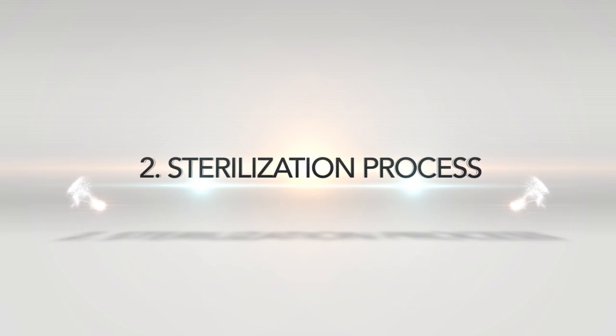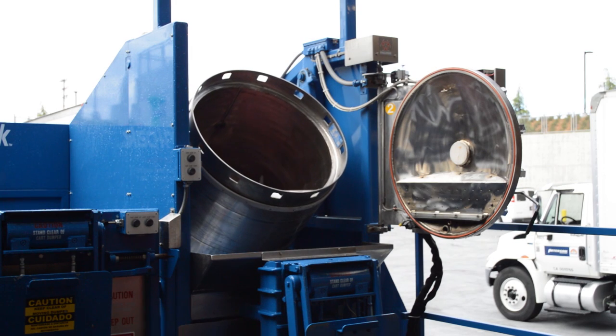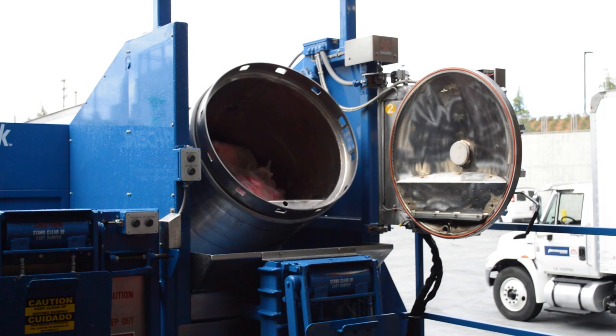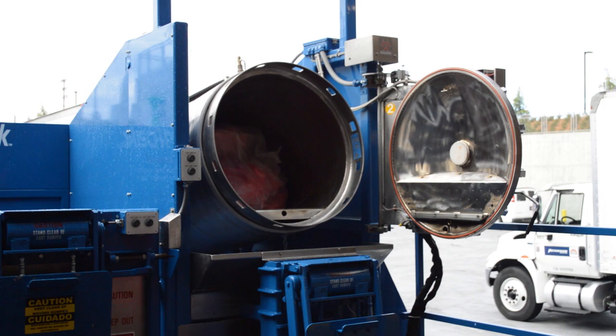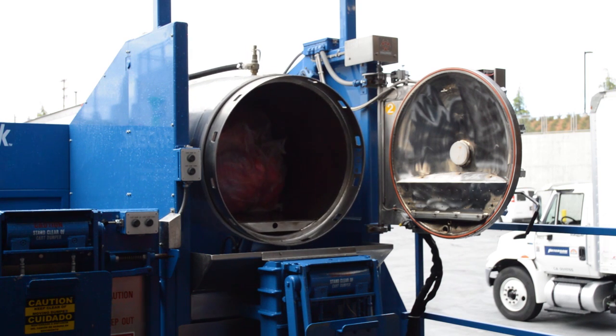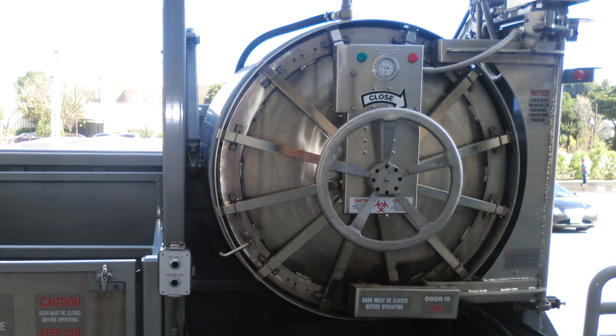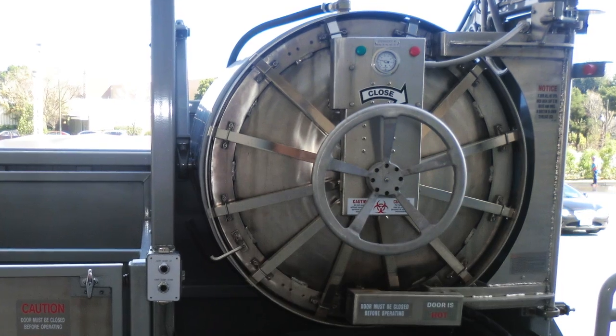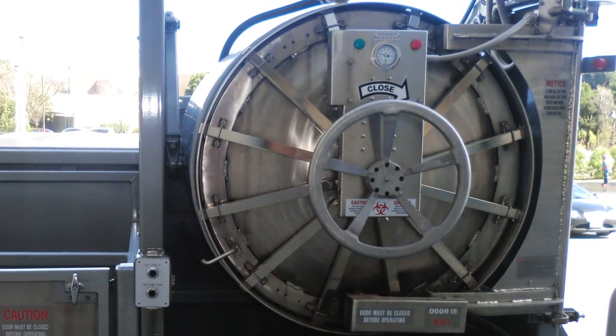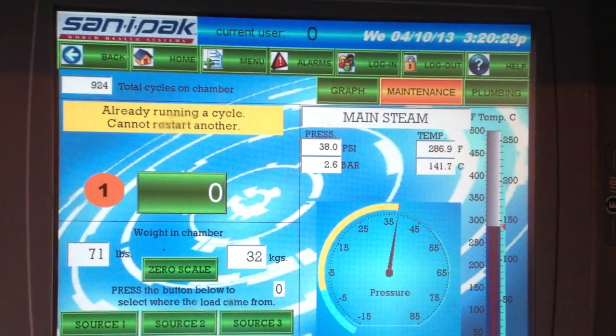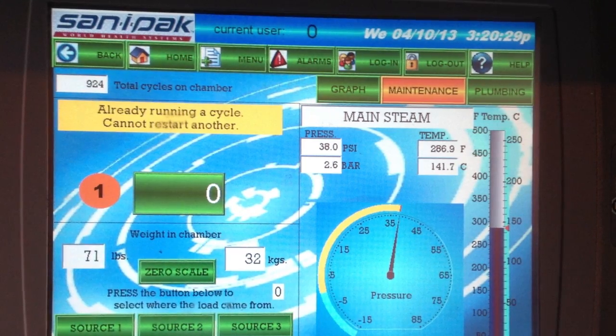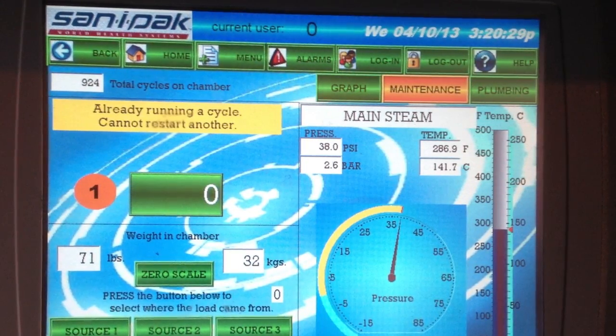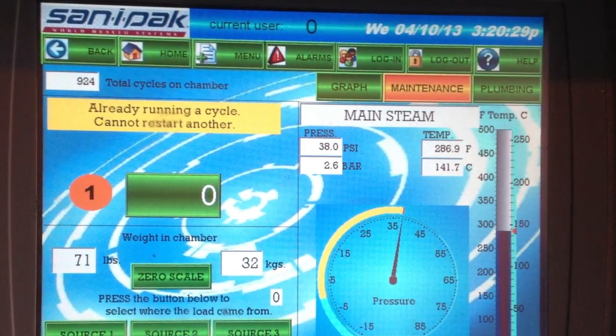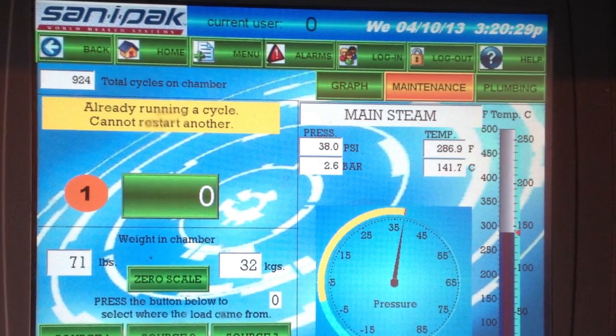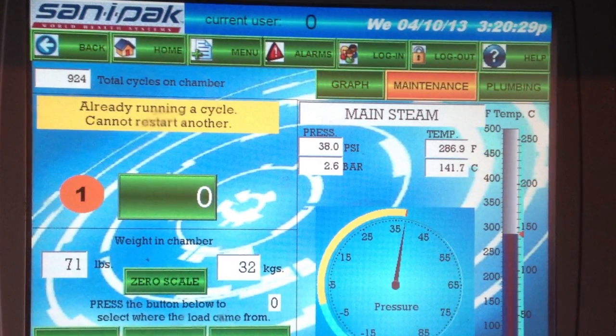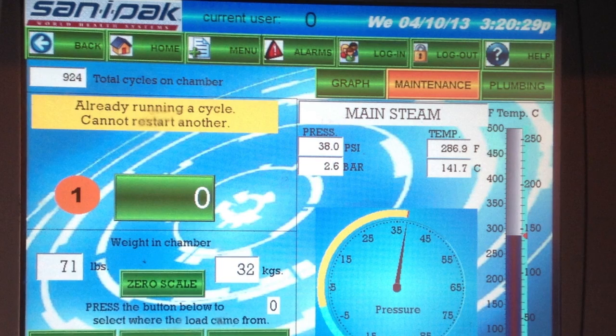Sterilization process. Once the sterilization chamber is loaded, it is placed in the horizontal position and the door is closed. The operator then initiates the sterilization cycle. The sterilization cycle includes a combination of high vacuum pulsing along with up to a 38 psi steam pressure. When the sterilizer reaches 270 degrees Fahrenheit, the 30-minute timer is activated. These treatment parameters meet and exceed all state and federal requirements for sterilization of infectious waste.